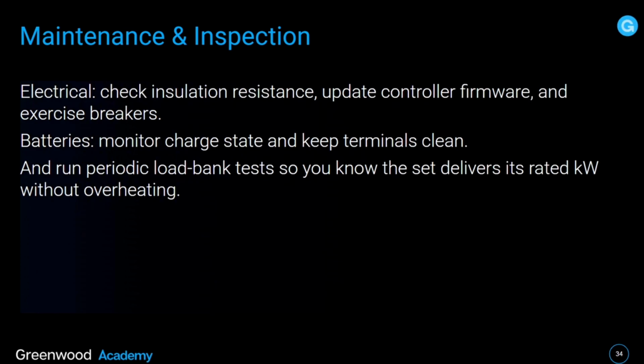Electrical, check insulation resistance, update controller firmware and exercise breakers. Batteries, monitor charge state and keep terminals clean. And run periodic load bank tests so you know the set delivers its rated kilowatts without overheating.